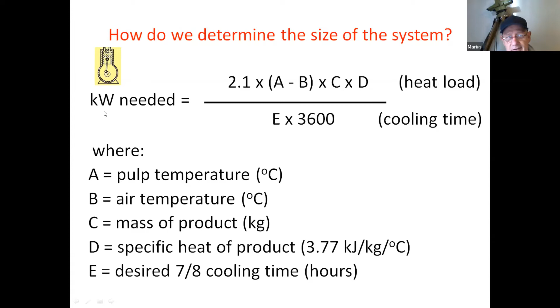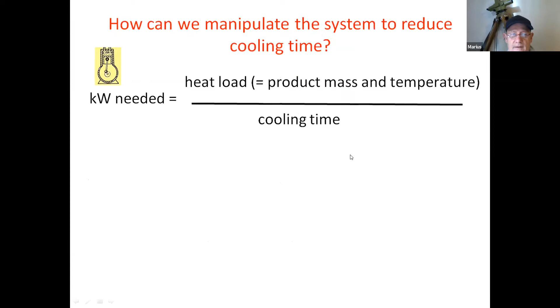And then the E at the bottom, the cooling time there, is the 7/8 cooling time. That's the desired time. If you want to reduce this cooling time, which is what's happened now in the industry in the table grapes, they went from 72 hours to 48 hours as their protocol. And that's where they stuck now, in terms of this little denominator, which has gone from 72 to 48. In other words, the numerator is being divided by a much smaller figure, which means the system design needs to change. They need more kilowatts to do the same amount of work for the same heat load.